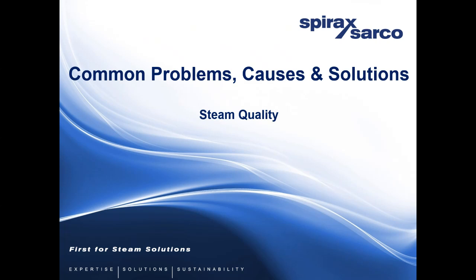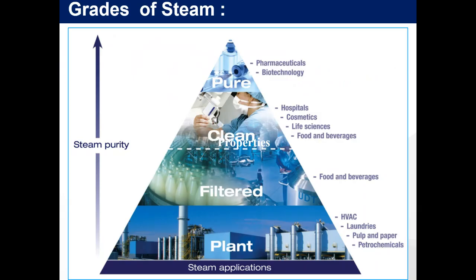So common problems, causes and solutions. We'll start with steam quality. As you can see, there are 4 main types of steam quality. Starting from the bottom is what most of you will see. For HVAC, laundries, pulp and paper, petrochemicals, you'll see plant steam. This is your typical steam system with no filtration, carbon steel pipes, SG or cast iron materials.